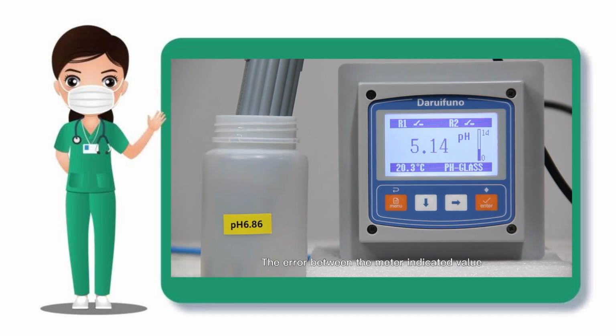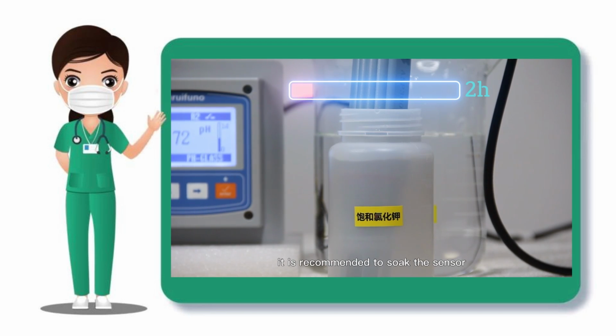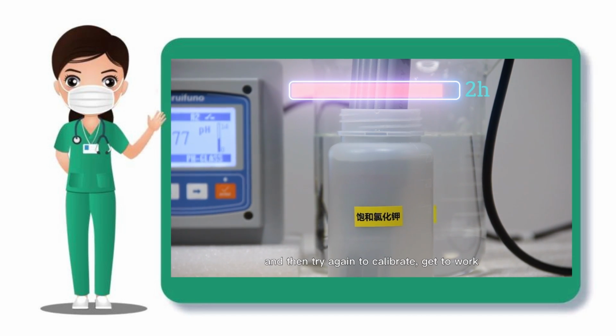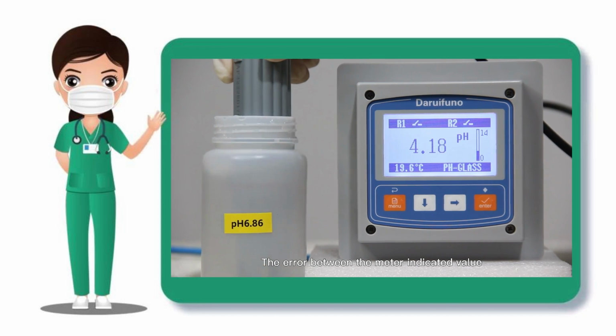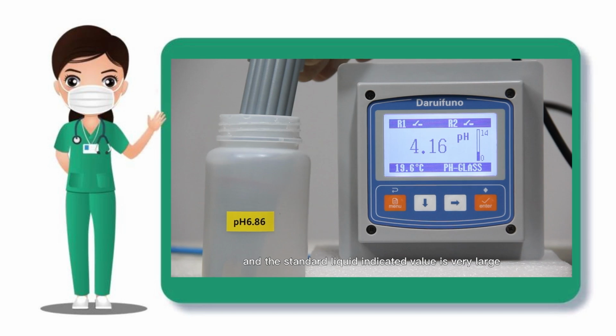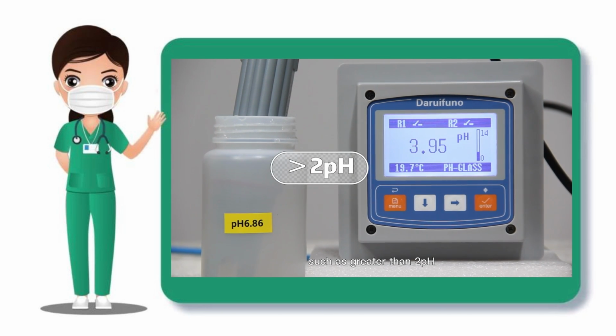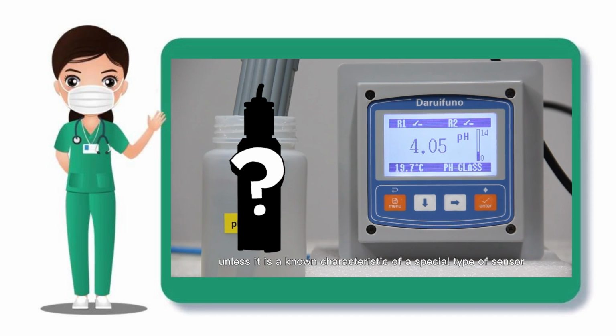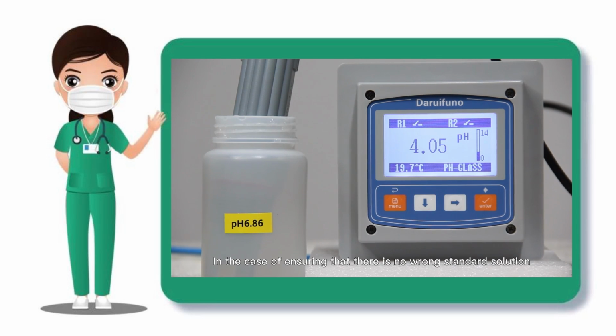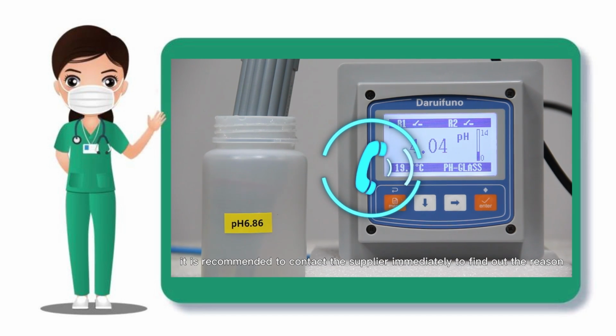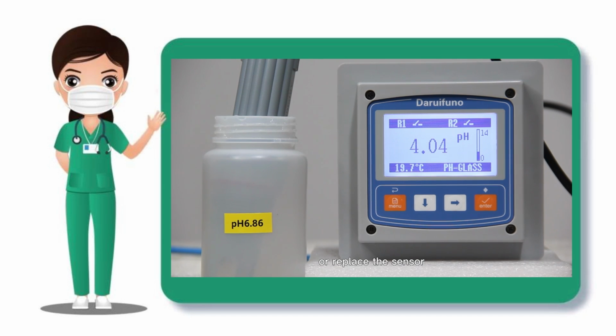The error between the meter indicated value and the standard liquid indicated value is relatively large, such as greater than 1 pH. It is recommended to soak the sensor in saturated potassium chloride solution for at least 2 hours to activate the sensor and return the sensor to the best state, and then try again to calibrate to get to work. The error between the meter indicated value and the standard liquid indicated value is very large, such as greater than 2 pH, unless it is a known characteristic of a special type of sensor. In the case of ensuring that there is no wrong standard solution or wrong connection, it is recommended to contact the supplier immediately to find out the reason, or replace the sensor.